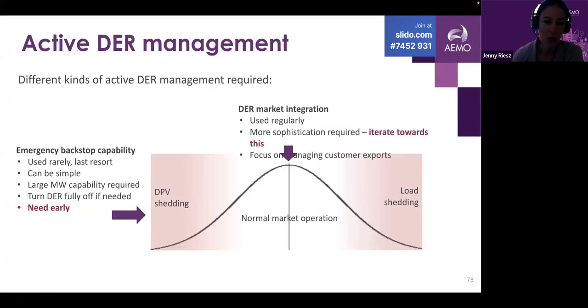Emphasizing again this point, we've been trying to put in place an emergency backstop capability, which you need early. It can be quite simple - you just need the ability to turn off very large amounts of PV if necessary in a security event. That's quite separate from full integration of DER into markets. There's a lot of talk about dynamic operating envelopes and distributors having nuanced control of distribution network limits. We absolutely need to go there, but it's a long journey. Well ahead of that, we've needed this cruder, simpler capability to turn off bulk PV for a security issue, and that's helping with learnings toward the more sophisticated capability.